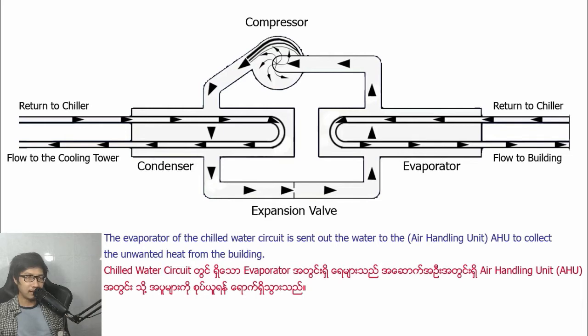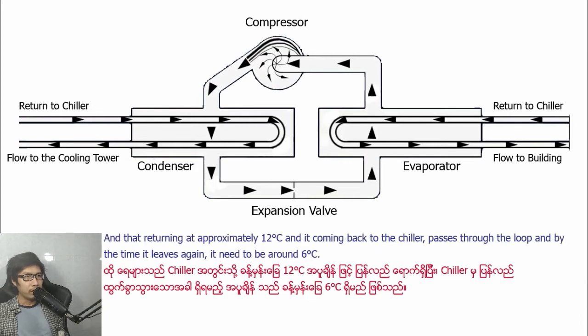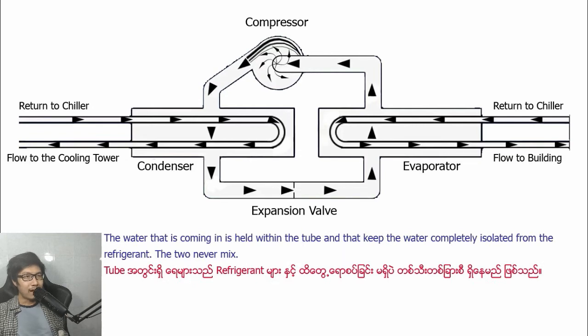The chilled water circuit from the evaporator sends water out to the air handling unit to collect the unwanted heat from the building, returning at approximately 12 degrees Celsius. It comes back to the chiller and by the time it leaves again it needs to be around 6 degrees Celsius. The water coming in passes through the tube and that keeps the water completely isolated from the refrigerant.